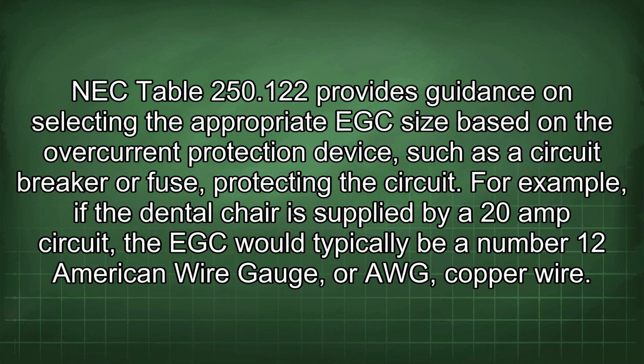NEC Table 250.122 provides guidance on selecting the appropriate EGC size based on the overcurrent protection device, such as a circuit breaker or fuse, protecting the circuit. For example, if the dental chair is supplied by a 20 amp circuit, the EGC would typically be a number 12 American Wire Gauge, or AWG, copper wire.